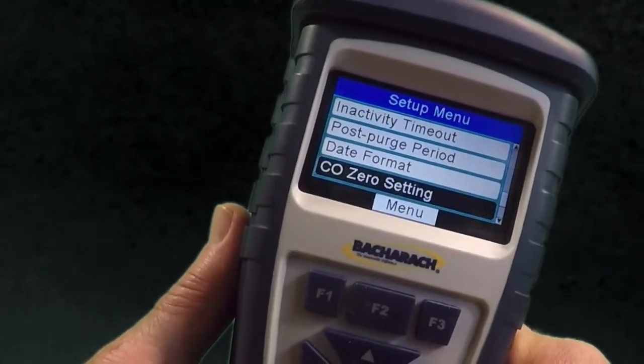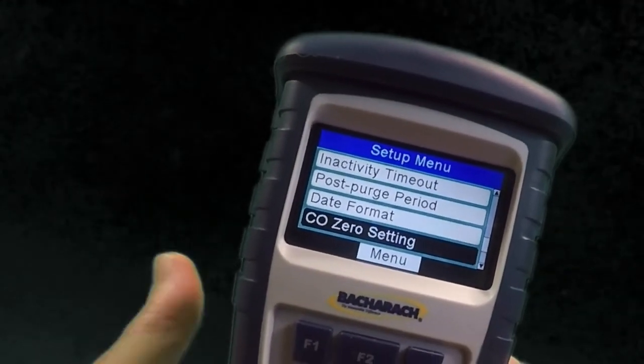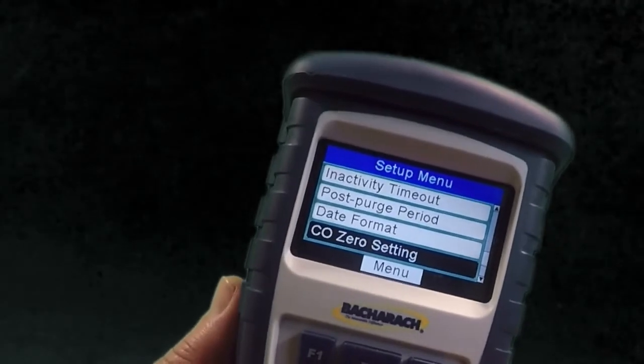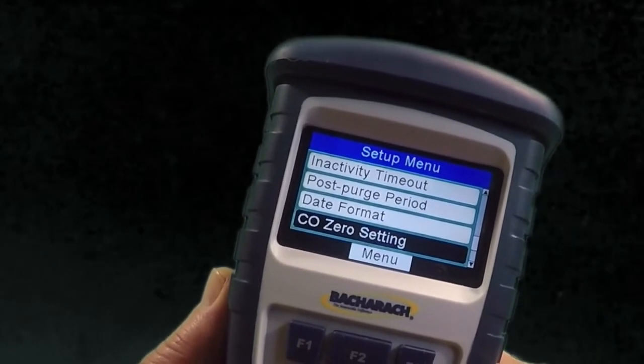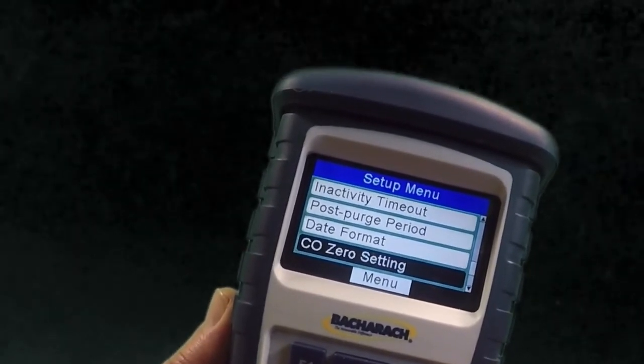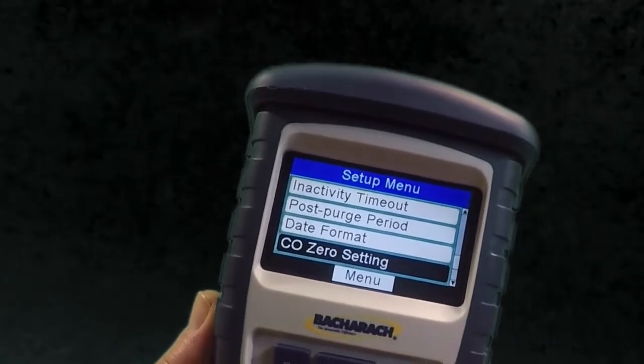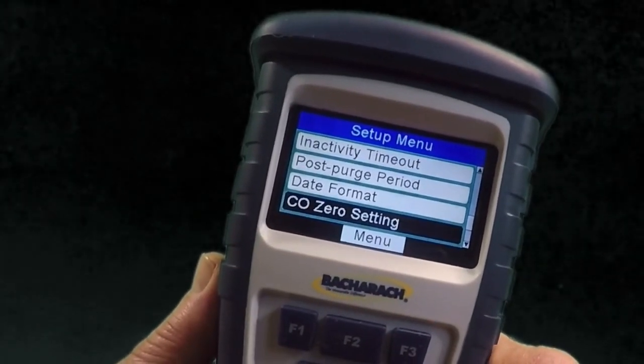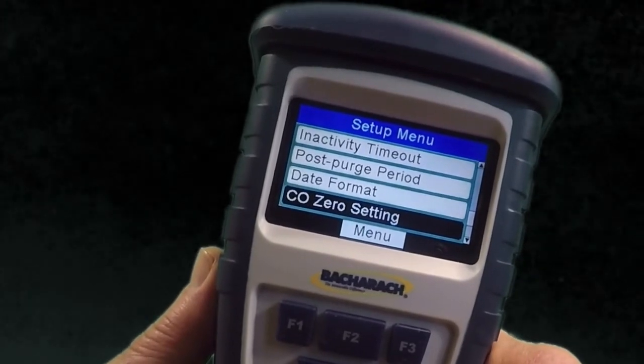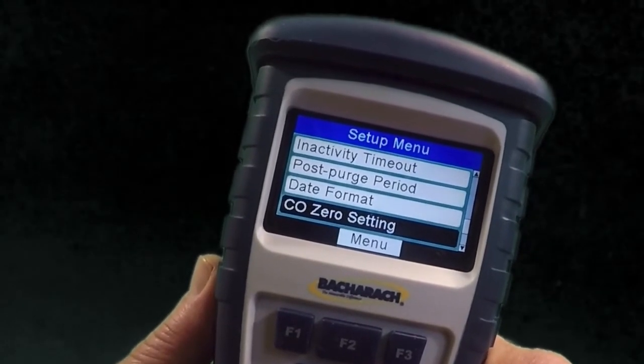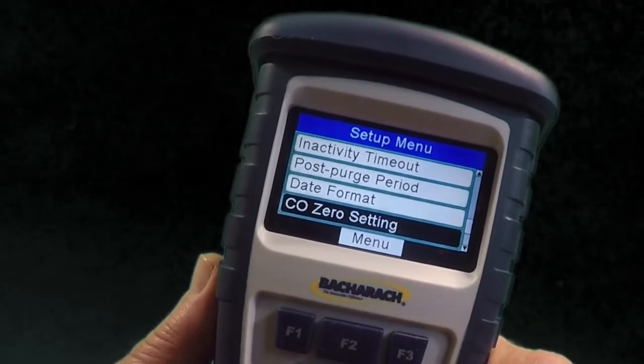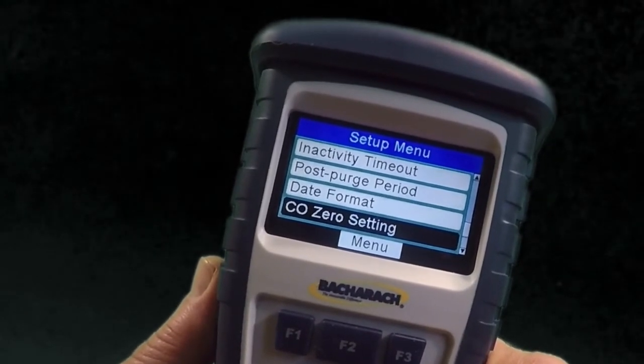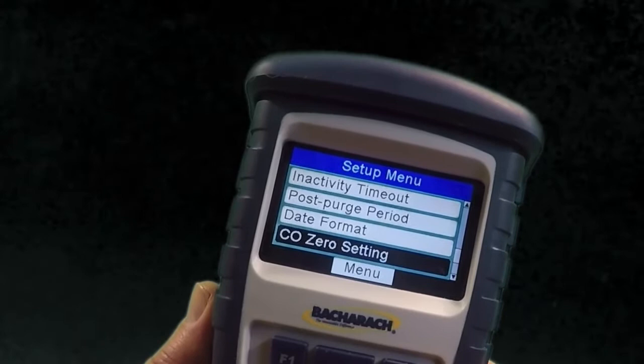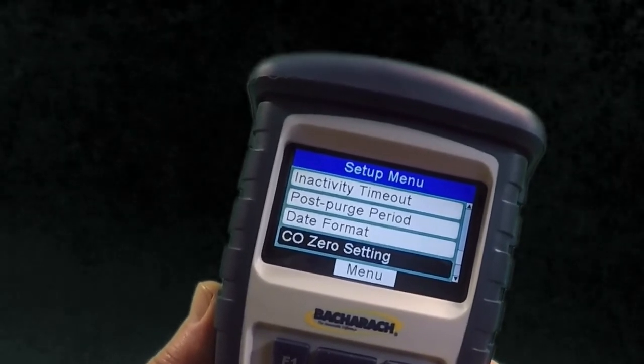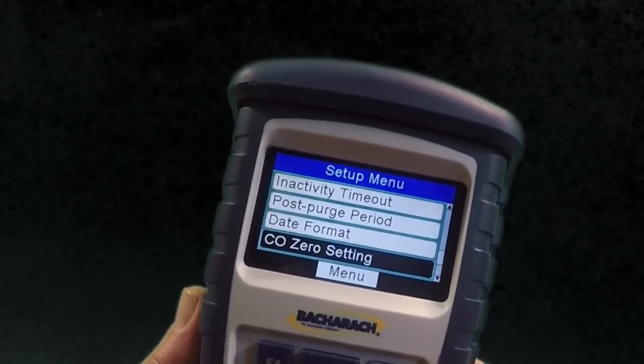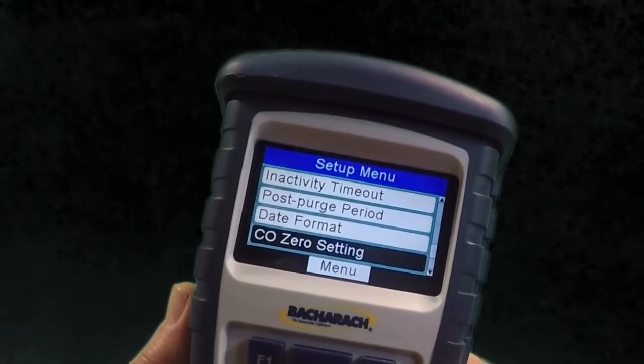All other manufacturers do only an auto CO0, and that's how Bacharach ships their instruments. Again, an auto CO0 means that the carbon monoxide sensor assumes the carbon monoxide level is 0 when you first turn the instrument on. For example, if we were in an area where there was 25 ppm, and I turned the instrument on and it's set up for an automatic 0, it's going to come up and read 0. This starts you out with a false 0, and more importantly, you'll be unaware that you're breathing a toxic gas.